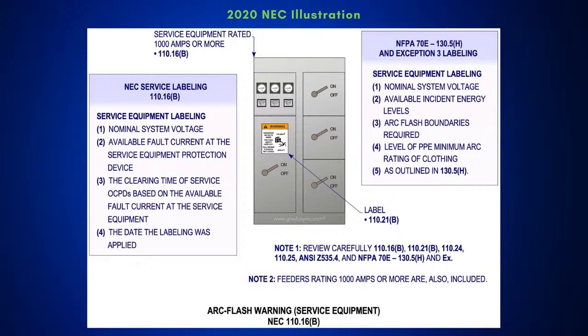Okay, gotcha. And when you look at Note 1 that we have here in the illustration, we tell you that you need to review a few things here. We're going to tell you to look at 110.16(B), which we're looking at. Also look at 110.21(B), 110.24, and 110.25. And then you've got your ANSI standard, Z535.4, which gets into the labeling. And matter of fact, we also come in the code now and talk about the coloring. Well, that's based on that ANSI standard. So if we're just signaling something, we do that in white or yellow. If we're giving a warning, we do it in orange. And if there's a danger, then we do it in red. Okay. Yep. And then right after that, we tell you to also look at NFPA 70E and look at 130.5(H). So we're laying this out in a systematic way so you know how to do the labeling for this piece of equipment.